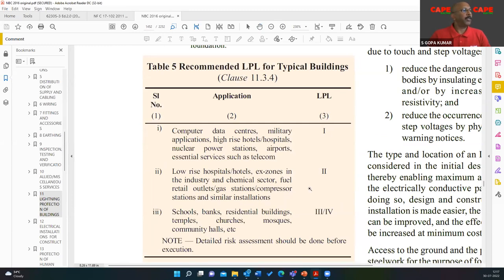Low-rise hospitals and Ex zones, you know, zone two. Then schools, banks, residential buildings, level three or four. This is a typical case. You can also do a risk assessment. That means once you ask us to do it, we will ask some questions or we send an Excel sheet to you. You have to fill up the sheet and we will make the calculations and tell you what minimum protection is required for your building. So based on risk assessment, you can make it. Either you go as per the NBC recommendation or you make a risk assessment.